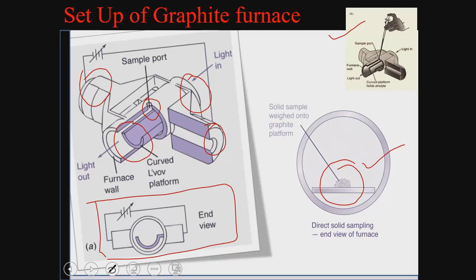In this inset picture you can see the process of sample injection, where we can put solid sample directly in microliter quantity. In this picture you can see the end view of the graphite furnace. The tube is encased within graphite electrical contacts at both ends that serve to heat the sample. So the sample is directly heated inside this graphite furnace. You can see the schematic diagram of the graphite furnace atomic absorption spectrophotometer. Here the furnace is kept in between the hollow cathode lamp and the monochromator.